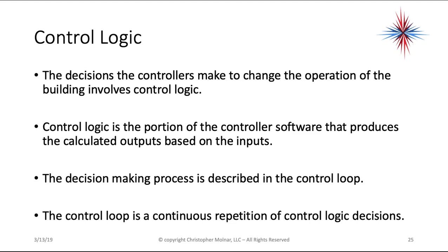Control logic is the decision the controllers make to change the operation of the building. It is the portion of the controller's software that produces calculated outputs based on inputs. The control logic uses this decision-making process in a control loop — a continuous repetition of control logic decisions. Just because it checks sensor temperature once doesn't mean it stops; it's continuous.